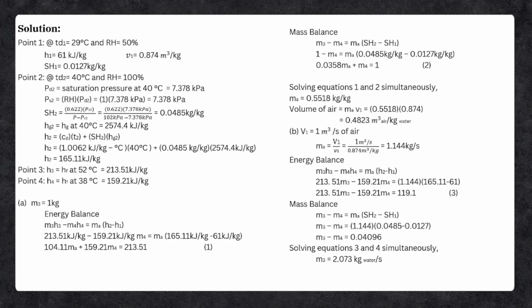For volume of air, our formula is MA multiplied by specific volume number 1. By substitution, 0.5518 multiplied by 0.874. So our volume of air is equals to 0.4823 cubic meter air per kilogram of water.